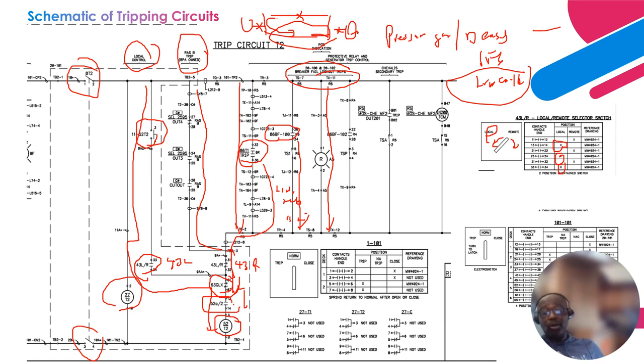The breaker failed to operate based on trip circuit T2. So it means that I need to operate trip circuit T2 and trip the breaker. Okay. Next is the trip circuit for the other breaker, right? The other one is basically the output from this relay, the transmission line relay, that should be able to trip this circuit. Then the next one is a trip coil monitor.